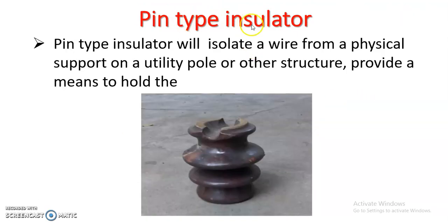First of all, the pin type insulator. The pin type insulator isolates a wire from the physical support on a utility pole or other structure and provides a means to hold the line, that is, the distribution line. It also provides isolation from the support or pole.